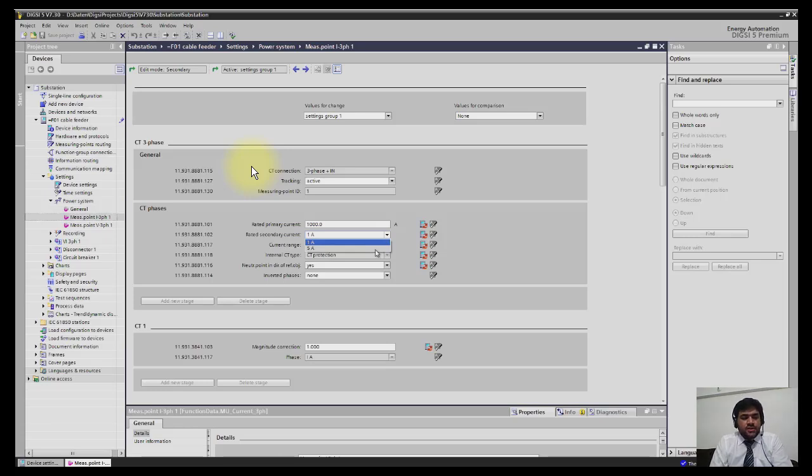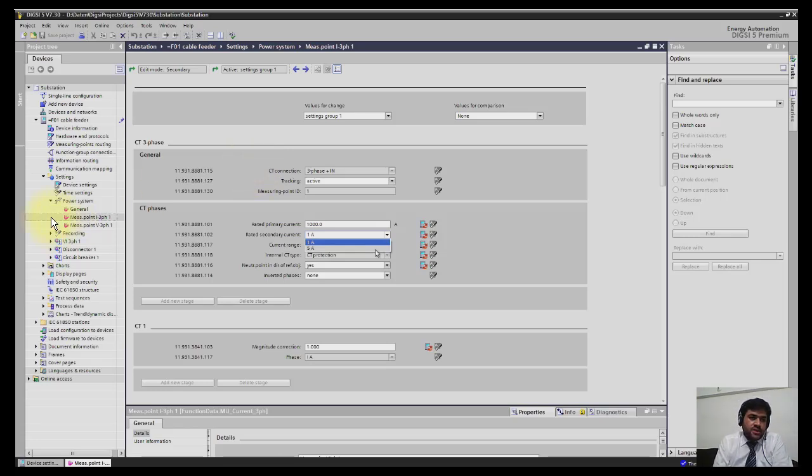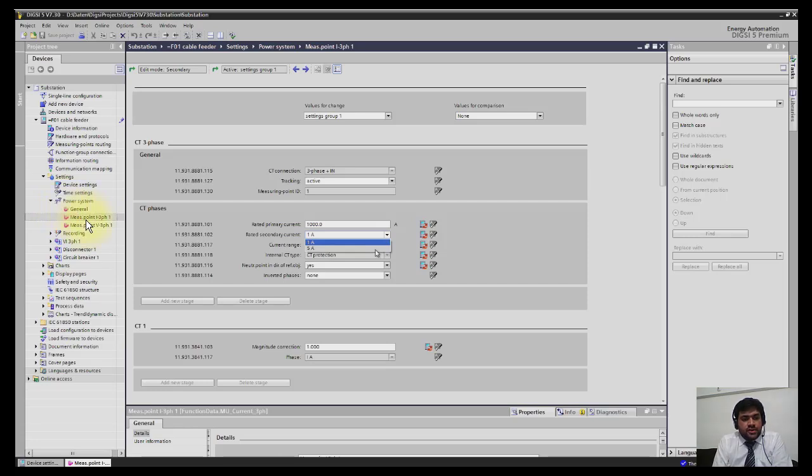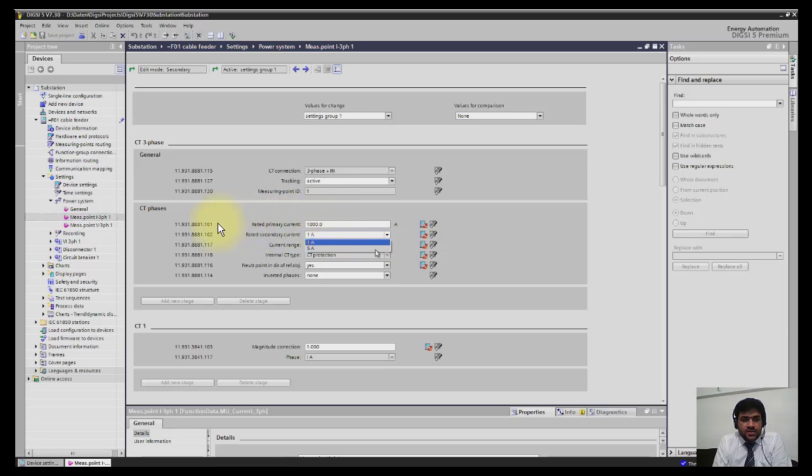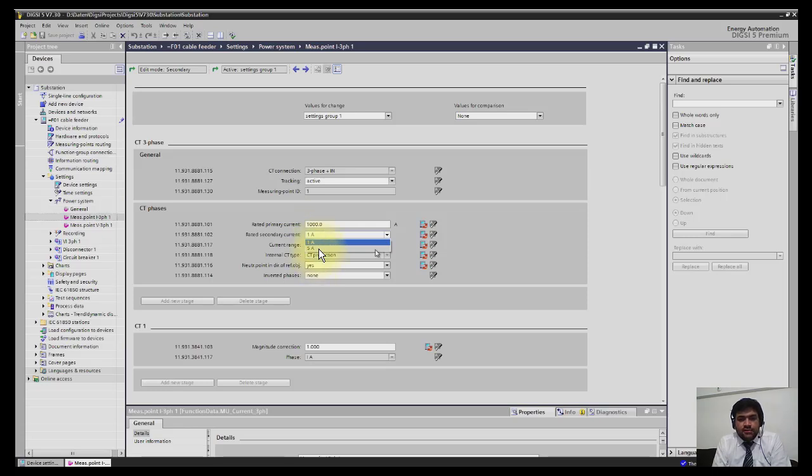Now we will move to another setting group: power system, which is available in the project tree. You can select measurement point three-phase single phase. Under CT phases, you can select the CT ratio here. For example, it could be 100:1 ratio or 100:5.